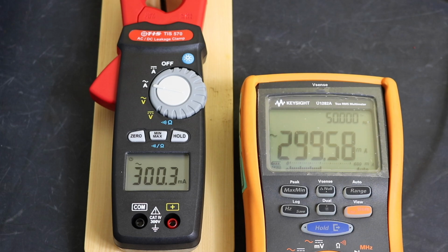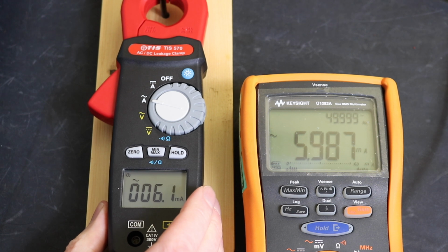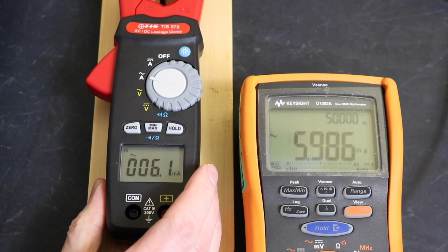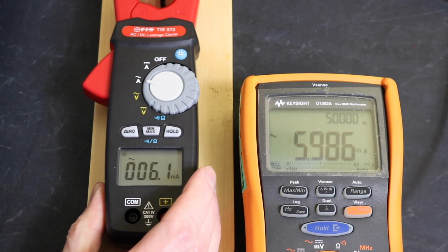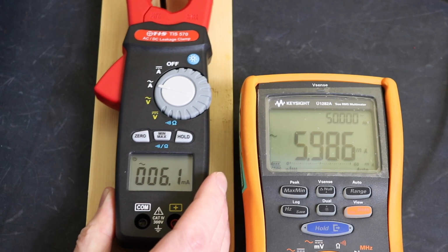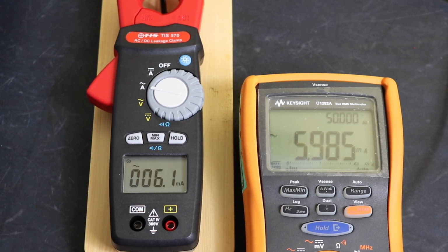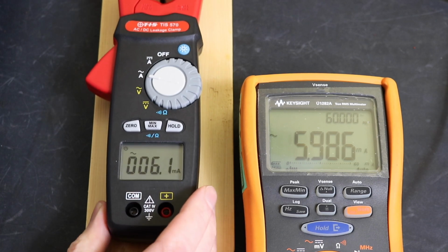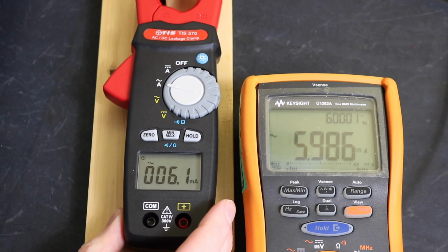We'll just take this all the way down to, let's go to our American friends who are on 6 milliamp RCDs. You can see we've got 6.1 milliamp there, 5.988. Let's shuffle our clamp around, and you can see this is a very, very stable clamp meter. It's not moved at all with regards to the position of the clamp. There's our 60 hertz there. Again, we're still all stable, no problems whatsoever.